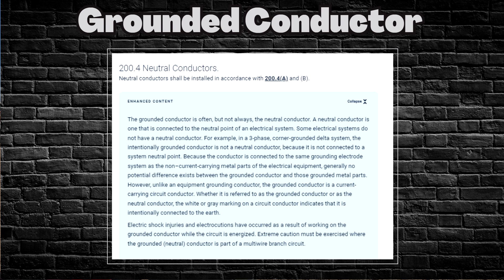Whether it is referred to as the grounded conductor or as the neutral conductor, the white or gray markings on a circuit conductor indicate that it is intentionally connected to earth. Electric shock injuries and electrocutions have occurred as a result of working on grounded conductors while the circuit is energized — extreme caution must be exercised where the grounded neutral conductor is part of a multiwire branch circuit. The key point is that the grounded conductor is a current-carrying circuit conductor, and in many cases — but not all — it is the neutral.